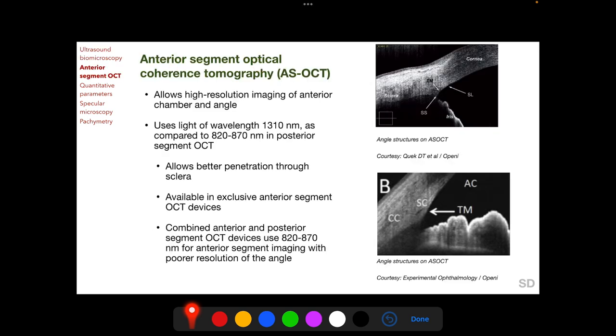Anterior segment optical coherence tomography (AS-OCT) allows high-resolution imaging of the anterior chamber and angle. OCT devices used exclusively for anterior segment imaging use light of wavelength 1310 nanometers, compared to 820–870 nanometer light used in posterior segment OCT devices. This 1310 nanometer light allows better penetration through the sclera and better imaging of the anterior chamber angle.